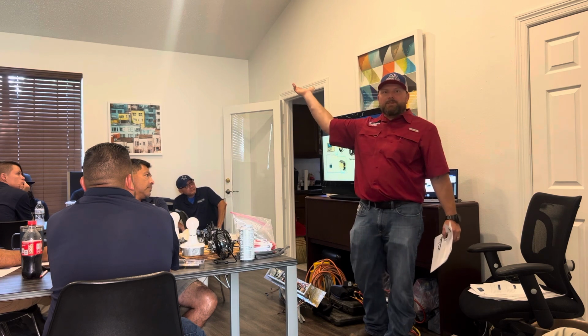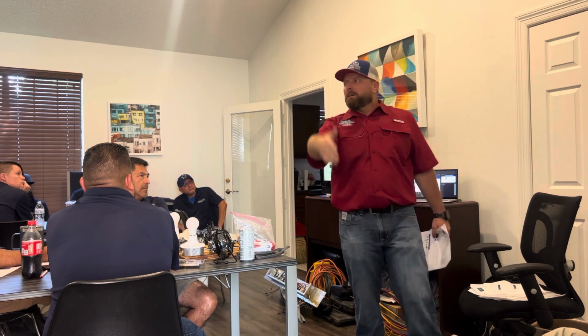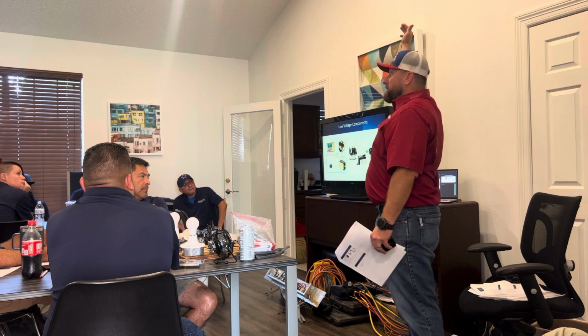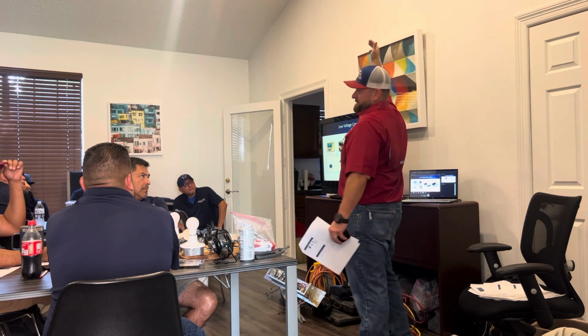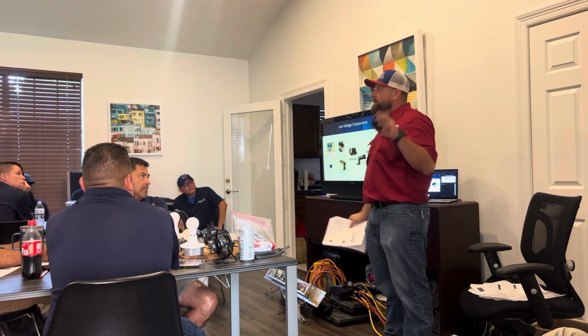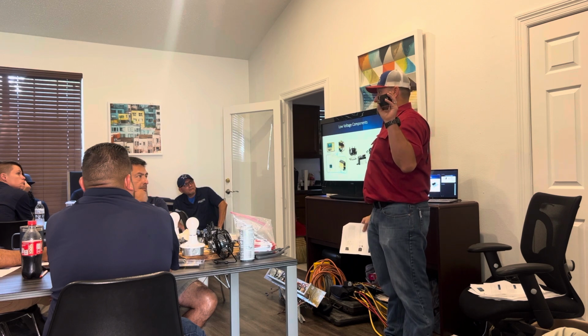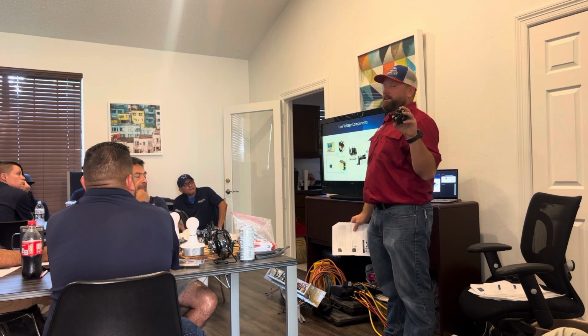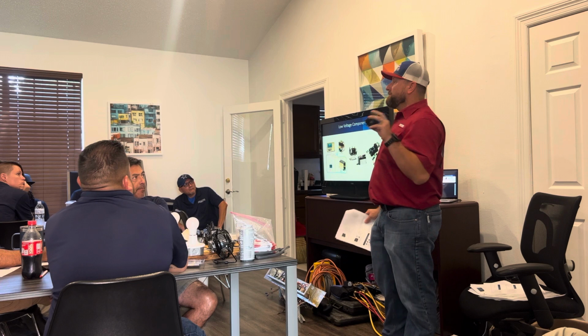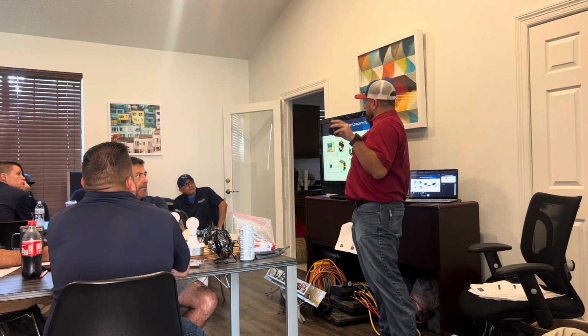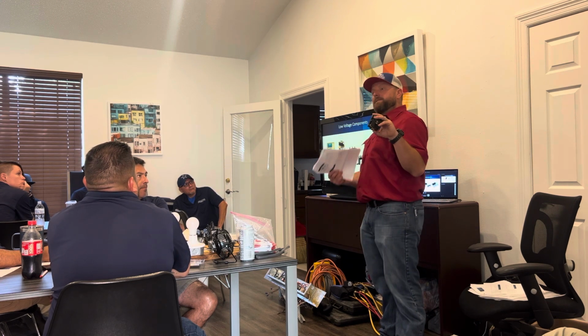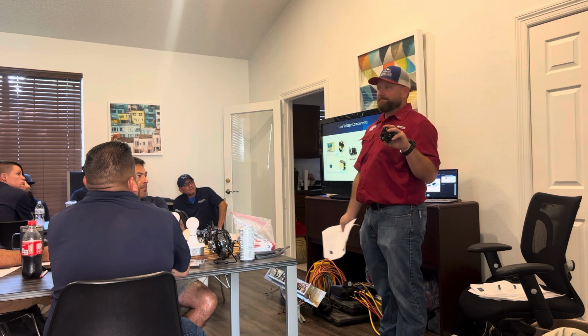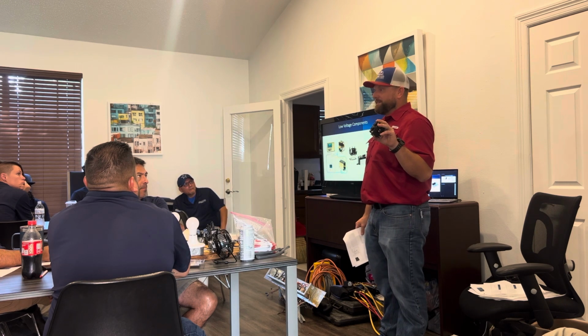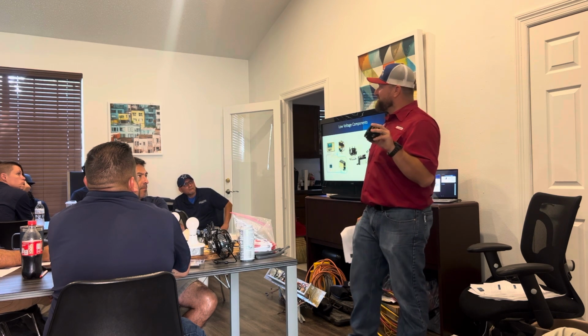You'll sometimes see 30 volts. If you go higher than 30 volts, it needs to be replaced, because then you're sending too much juice to these components and they'll start frying. If you don't have 24 volts, and it's only doing like 15, sometimes you'll hear this thing chattering. Have y'all heard that before? It's just really struggling.